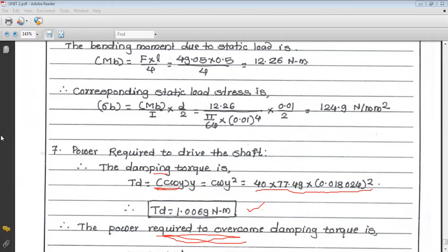So the power required to overcome this damping torque is 2 pi N T upon 60 into 1000. It is in watt. So 2 pi N is 740, torque is 1.0069, divided by 60 into 1000. So that value is 78.07 watt. This is the power required to overcome damping torque only.